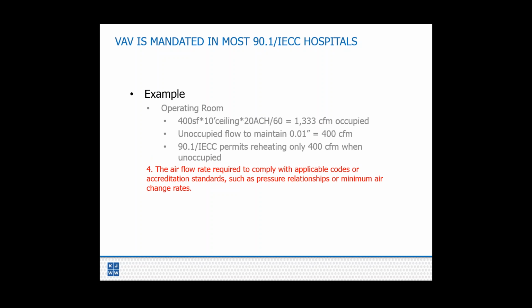But again, 90.1 and the IECC only permit reheating that 400 CFM when the space is unoccupied. So from a code standpoint, it's actually required in those energy codes. Again, it makes it a VAV system. Next slide, please.